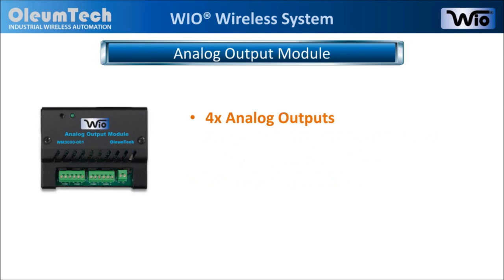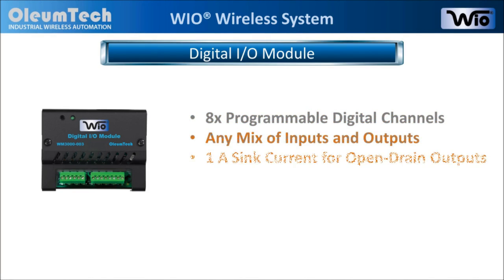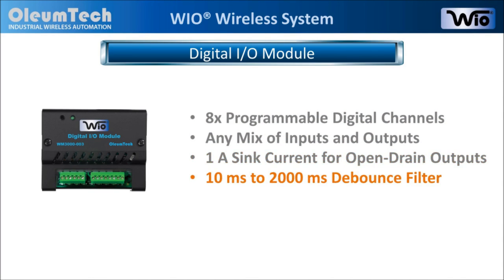The analog output module is equipped with 4 analog outputs and supports 1-5V and 4-20mA outputs. The digital IO module features 8 programmable digital channels where inputs and outputs can be mixed in any way. It also features a 1-amp sink current for open-drain outputs, and 10ms to 2000ms debounce filter.